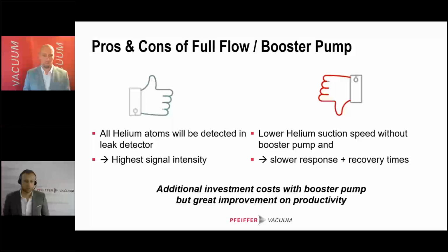But what we can assure you and what we usually always consider when we have a high cycle time requirement and a leak rate that is in the right ratio, is the usage of a booster pump. Of course, it has an additional investment cost at the beginning and the layout, but we would say the great improvement in productivity enables a very fast return on investment.